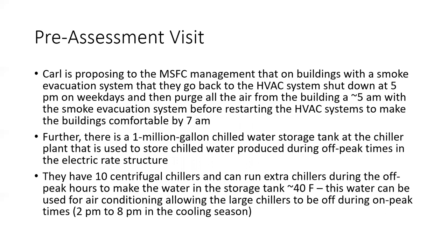And so then they would run this HVAC system to purge all of the air from the building for whatever period of time. My calculation, I would think it would be between probably 20 minutes and an hour. That'll be one thing that we'll want to evaluate, how long they need to run the evacuation fans in order to purge the building. And that's a simple calculation. You just take the volume of the building and the CFM of the fan and divide the volume by the CFM. That tells you the number of minutes you have to run it in order to turn over that amount of air. We just have to calculate the volume of the building and know something about the evacuation system.